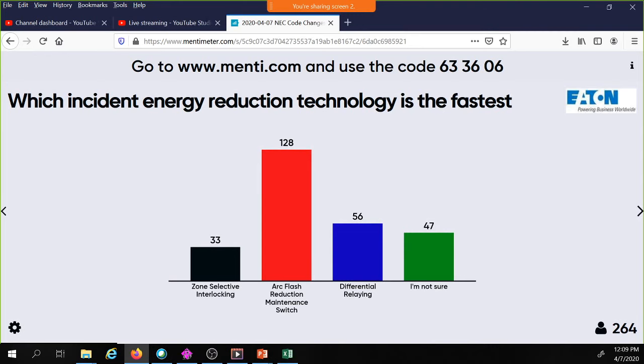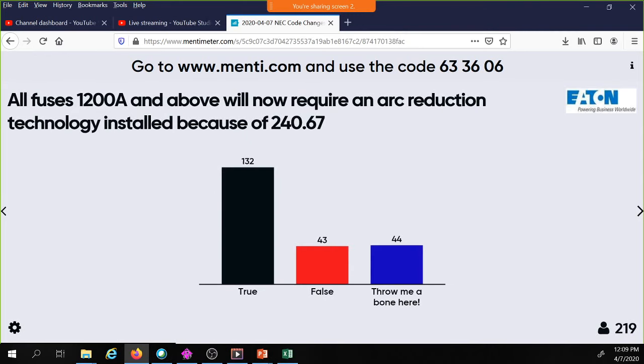All right. So our arc reduction maintenance switch was the right answer on that one. How about: all fuses 1200 amps and above will now require an arc reduction technology installed because of 240.67. We have an overwhelming 138. See, now they're piling on. People are logging on to Menti. They're seeing that big black bar there that's 140 people, and they're jumping on that bandwagon.